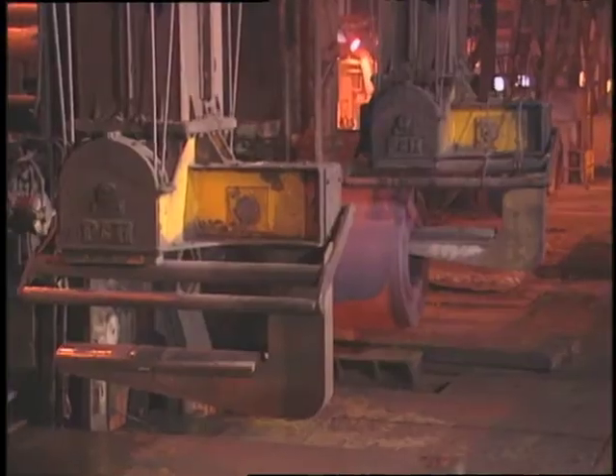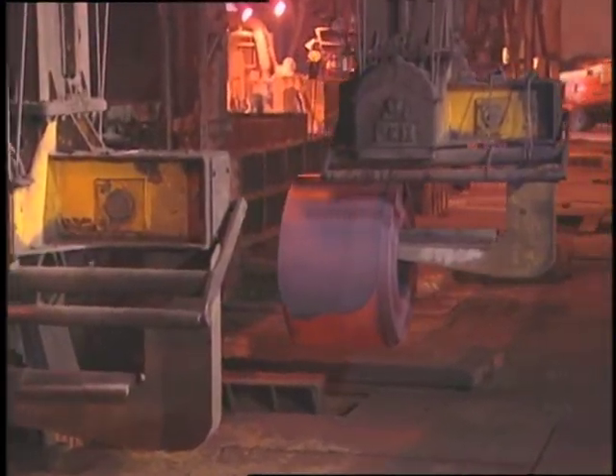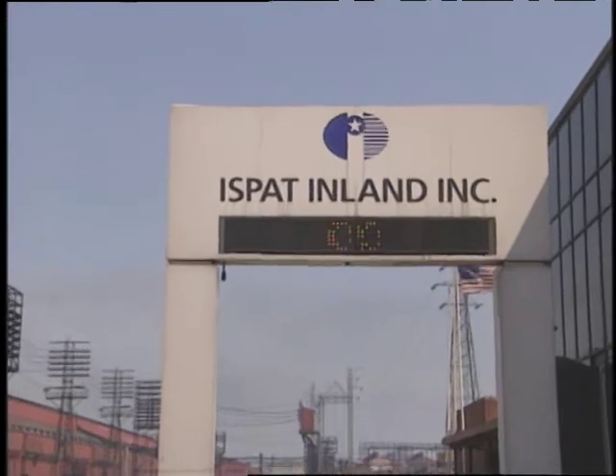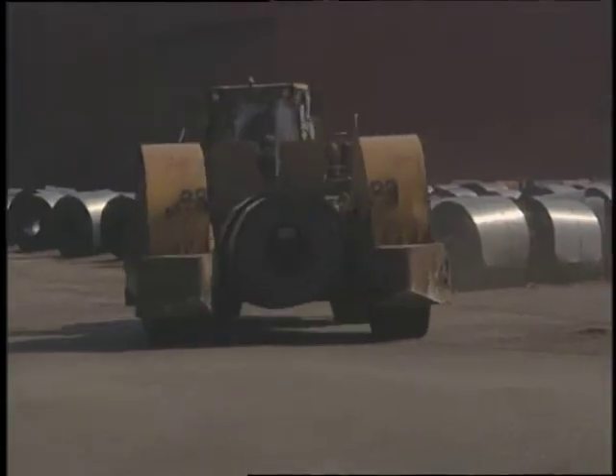So if we look at what we call our basic KPIs that we use to justify this capital investment, one of the KPIs was a 0.3 MMBTU per ton reduction in fuel consumption for the new furnace, and that we've achieved. The existing furnaces were running at around 1.7, 1.6, depending on where they're at in their repair cycle. The new furnace very clearly came in at 1.2. And so we've met that energy savings goal.